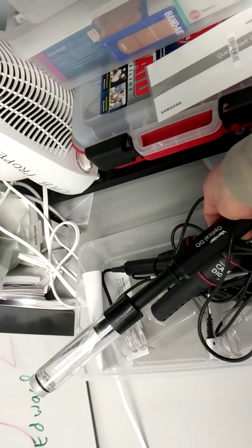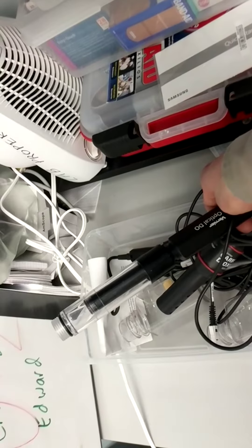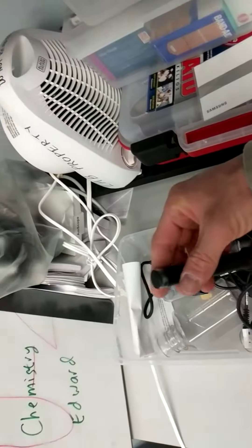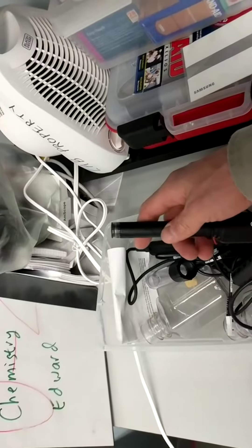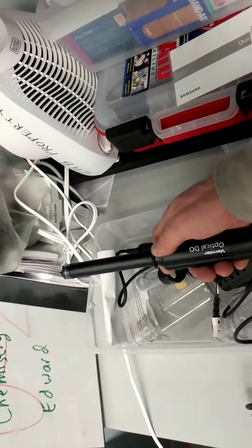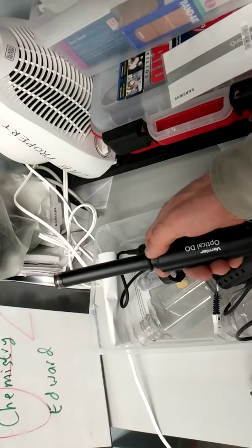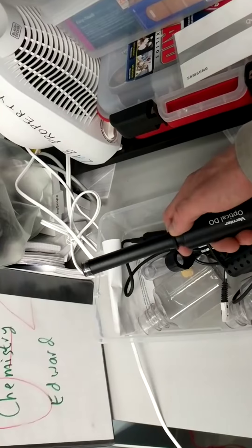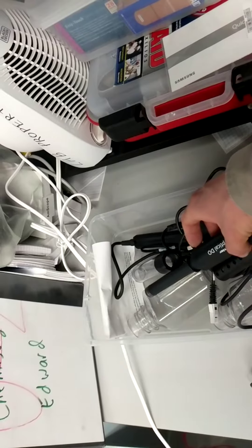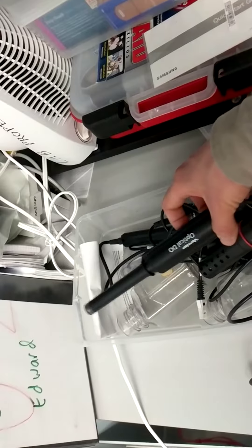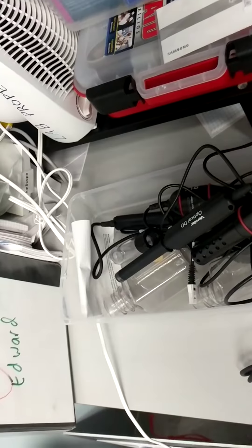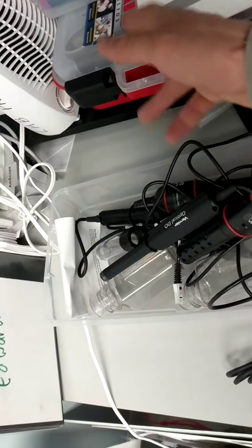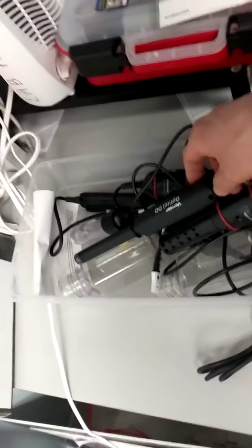So that's how this thing works. This is a very fancy piece of equipment. This directly measures oxygen, and here's how it does it: there is a solid plastic wafer in here impregnated with this dye, and the dye fluoresces in the presence of oxygen. So this thing is measuring fluorescence of that plastic wafer that contains dye. It's very convenient that you don't need to calibrate it. The usual dissolved oxygen sensor, which was called the polarographic sensor, had to be calibrated with a couple of different solutions and it was horrible to use.